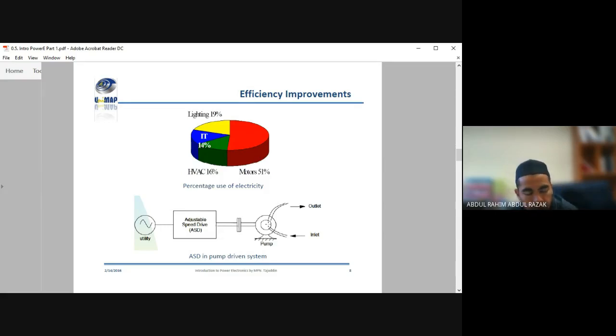If you learned your electrical drives, or in the machines that we have learned before, when we switch on the AC motor, there will be an inrush current of about 5 to 10 times the rated current. Let's say the motor needs only 10 ampere. So the starting current can go up to 50 amps or up to 70 or 100 amps, depending on the efficiency of your motors. So when you start and stop with that kind of direct online application, you might break your pump, you might break your pipe, and you might break your wallet, because it costs so much when you start and stop.